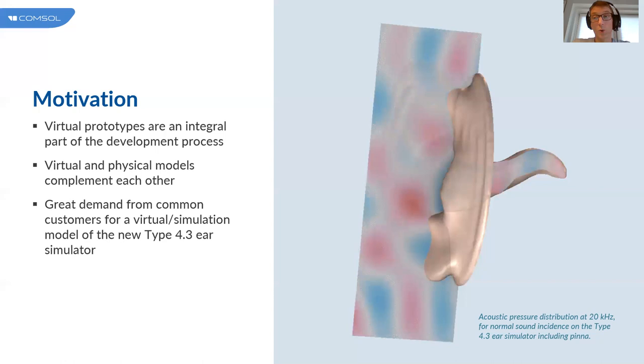We saw a great demand from common customers of HBK and COMSOL for a virtual simulation model of the new Type 4.3 Ear Simulator to make sure that you could actually do the same virtual measurements and tests as you could with physical tests. This was really the main motivation for the work I'll be presenting today. The animation to the right shows the acoustic pressure distribution at 20 kilohertz for normal sound incidence on the Type 4.3 Ear Simulator including the pinna. It's an open ear situation and a high frequency response of the system as you can see from the wave pattern.